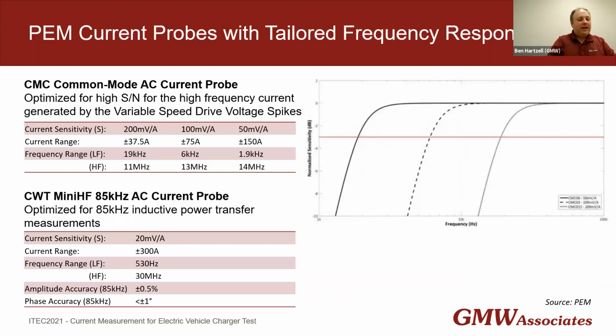PEM Rogowski coils can be tailored to specific frequencies. So we're attenuating the frequencies outside our area of interest. I have two types of examples shown here. The first is a CMC common mode current AC probe. Looking here at the specs, you can see that the current range is fairly moderate, 40 to 150 amps, with a lower frequency cutoff of 2 kilohertz up to 20 kilohertz, and a high frequency cutoff of 11 megahertz to 15 megahertz. Here you can see on the plot, it is very linear until that roll-off cutoff point.